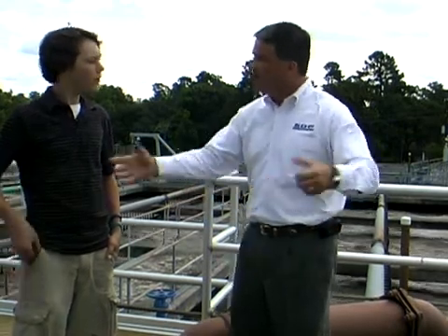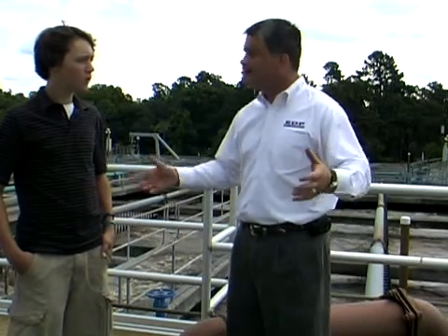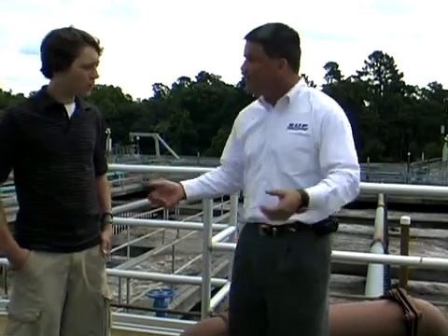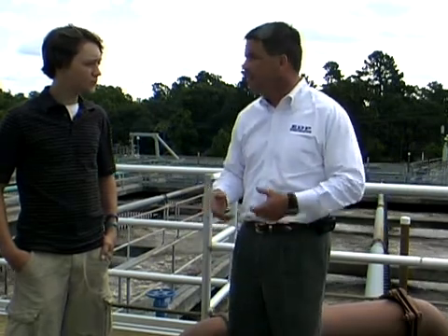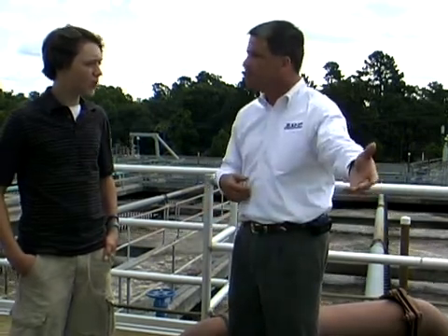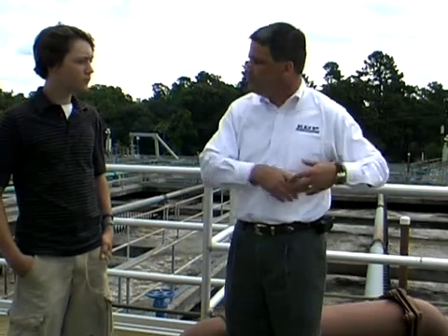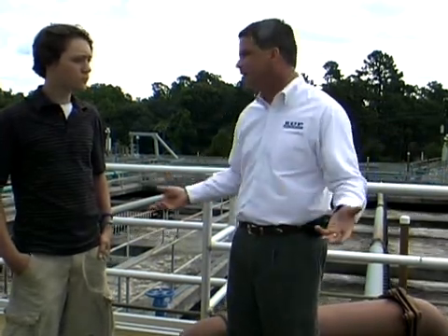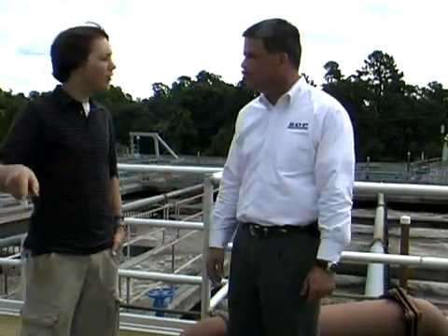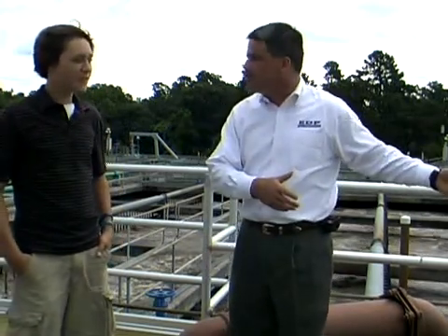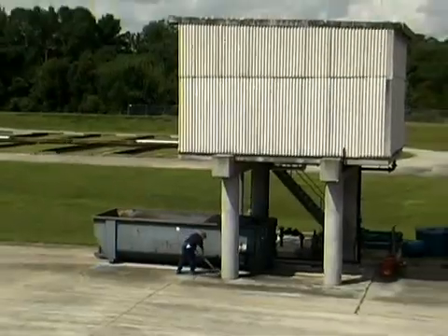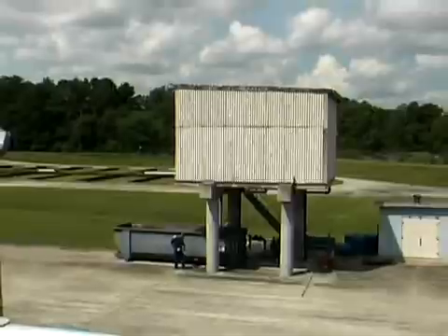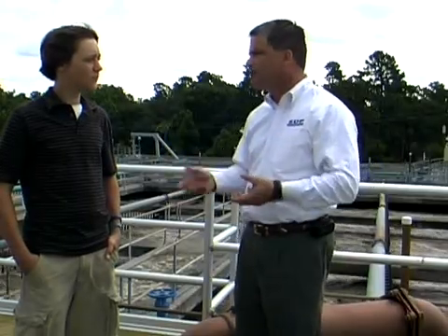So I may have 35 or 40,000 or 50,000 pounds of bacteria that I grow in this plant. Eventually I reduce that down to about 20 or 25,000 pounds of bacteria that eventually leaves the plant site. So the digesters help us to reduce the total amount of bacteria that we have to handle. Where does that go? Okay, when we're done handling it in the digesters, then it goes over to a sludge press. Over here we have a sludge press, and we'll take a look at that.